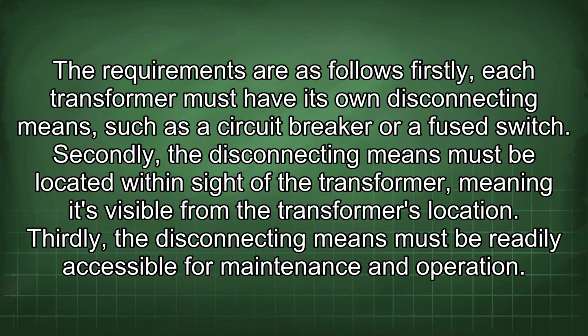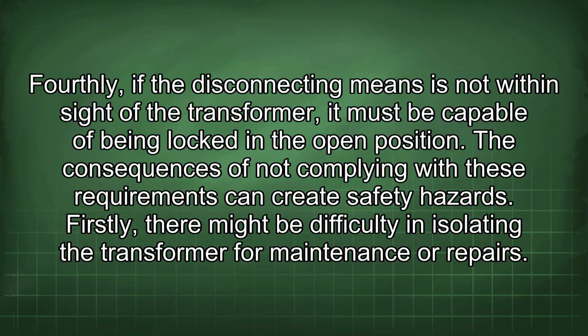The requirements are as follows. Firstly, each transformer must have its own disconnecting means, such as a circuit breaker or a fuse switch. Secondly, the disconnecting means must be located within sight of the transformer, meaning it's visible from the transformer's location. Thirdly, the disconnecting means must be readily accessible for maintenance and operation.